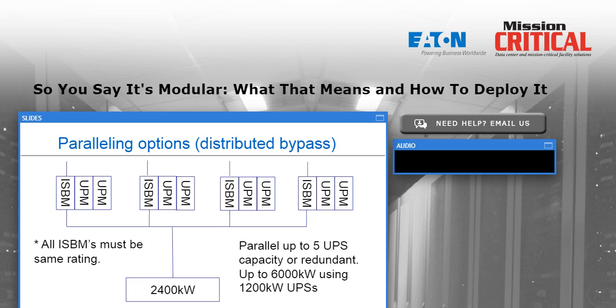Can your system work at 575 volt or 4160 volt applications? We can do 575. There are a few UPS vendors that can do medium voltage, 4160 volts, for example. I would say the bulk of the data center applications are 480 volts or 575 or 600 volts up in Canada. When we make the jump to the medium voltage, as you can imagine, there's significant differences in electrical insulation needs and safety requirements and things like that a lot of us vendors are just a little bit nervous about. But if you check on the internet, you will find there are vendors of UPS products that do provide medium voltage or greater than 600 volt capabilities with their UPS.